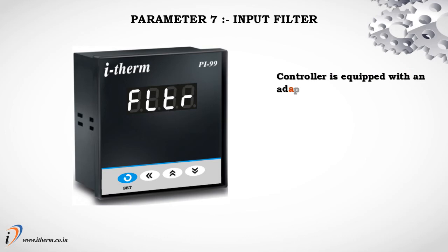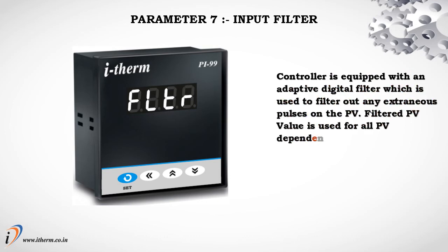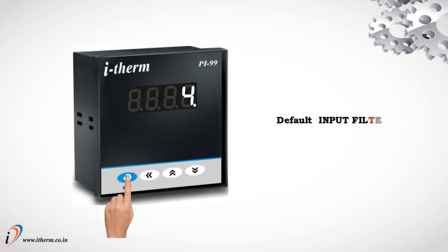Parameter 7: Input Filter. The controller is equipped with an Adaptive Digital Filter, which is used to filter out any extraneous pulses on the process value. The filtered process value is used for all process-value-dependent functions. If the process value signal is fluctuating due to noise, increase the filter time constant value. The default Input Filter Value is 4.